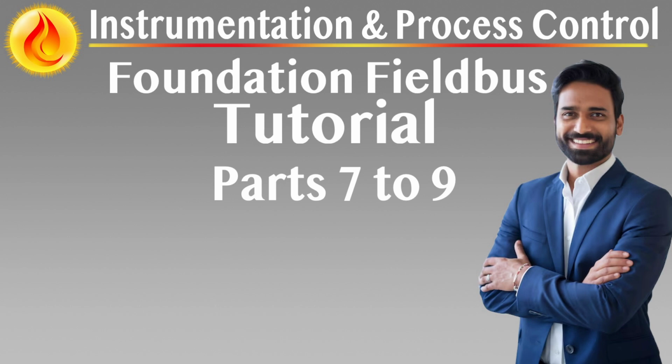Virtual Field Devices, VFDs. Virtual Field Devices, VFDs, are the logical containers within Foundation Fieldbus devices that encapsulate all the functions, data objects, and services necessary for a device to participate in a Fieldbus network. While a physical device represents the hardware, the VFD is the digital model of that device from the network's perspective. It abstracts the internal resources, such as function blocks, transducer blocks, system management components, and communication interfaces, into a structured, addressable form that ensures interoperability and standardized behavior across the network.